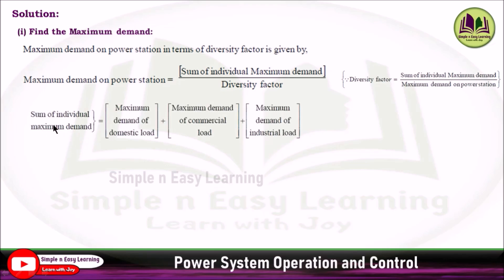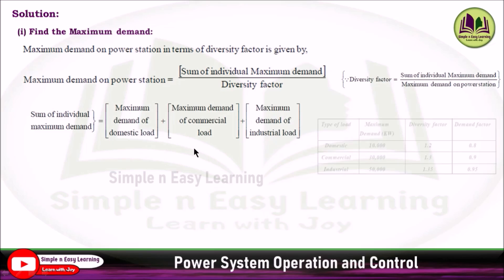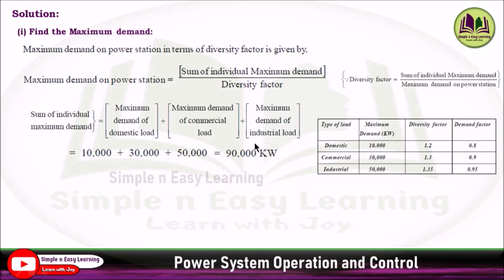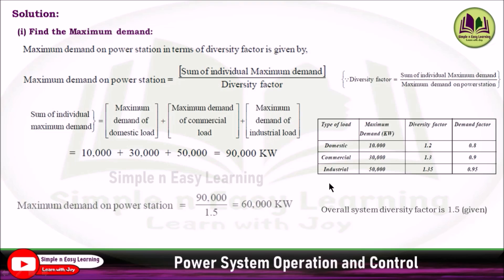The sum of individual maximum demands equals the maximum demand of domestic load plus maximum demand of commercial load plus maximum demand of industrial load. These three loads are specified in the problem. Using the table, substituting directly: 10,000 + 30,000 + 50,000 gives 90,000 kilowatt. The overall system diversity factor is 1.5, so dividing 90,000 by 1.5 gives 60,000 kilowatt — this is the maximum demand on the power station.